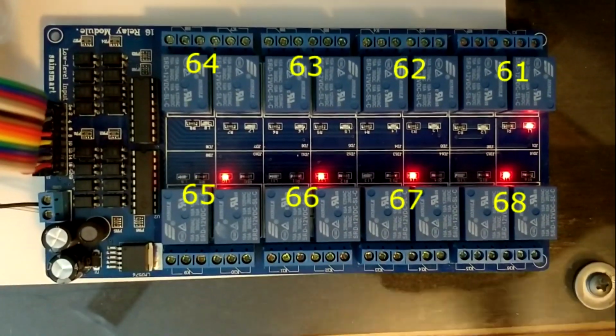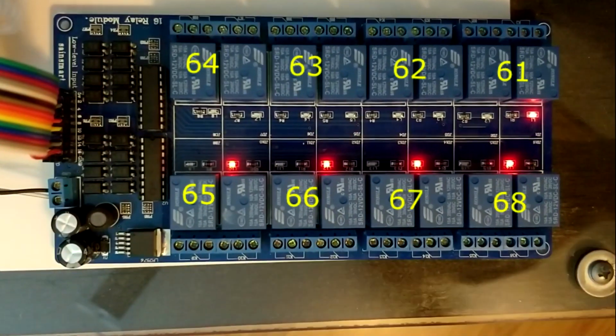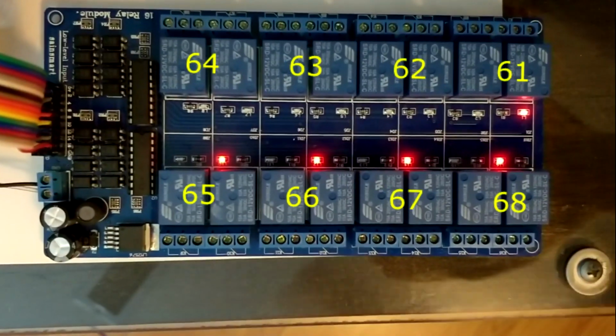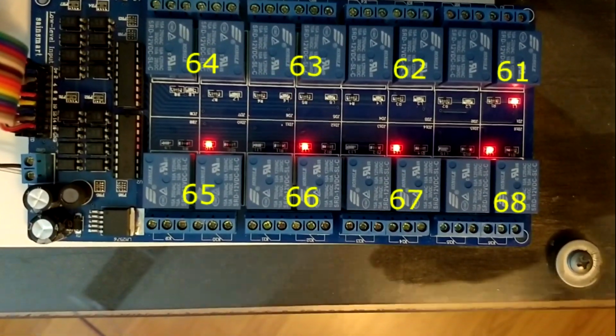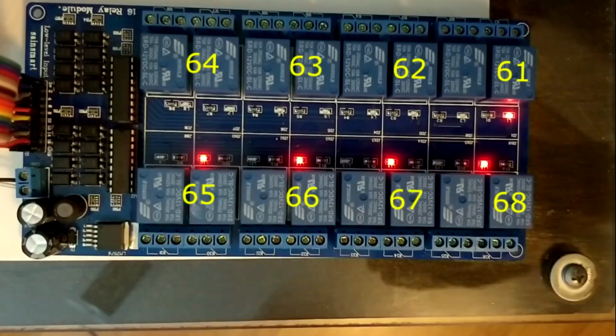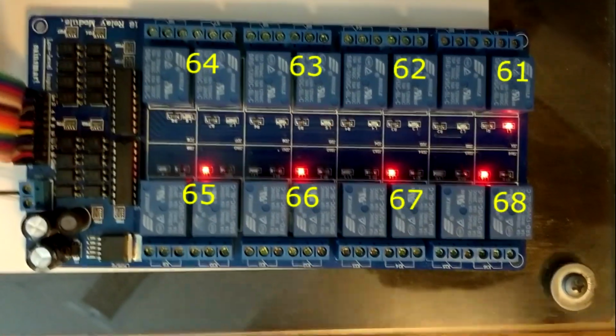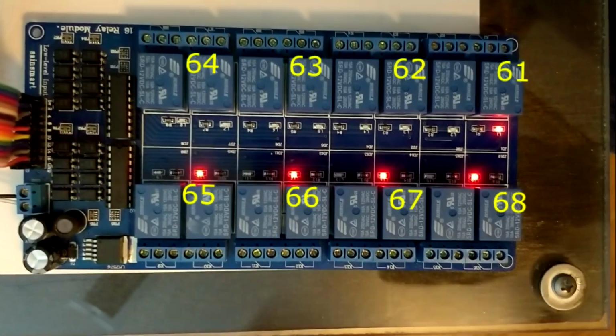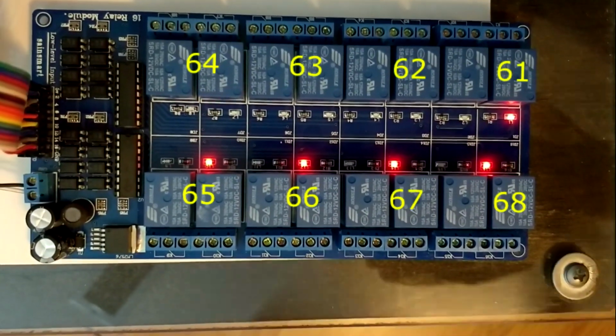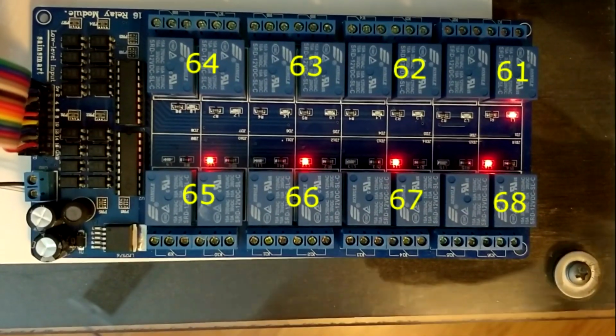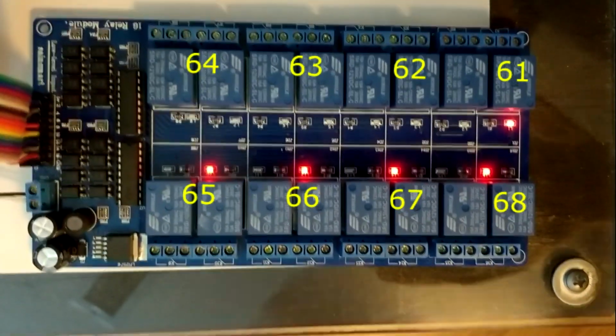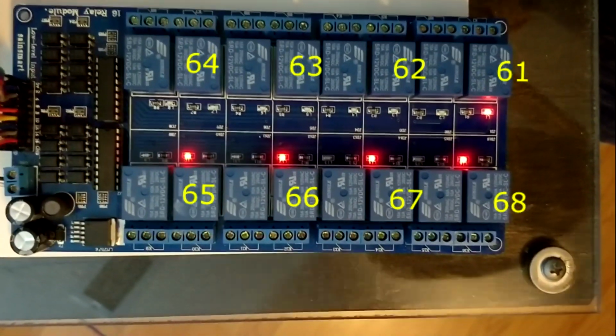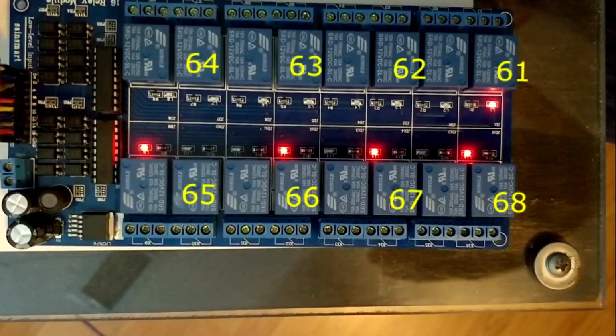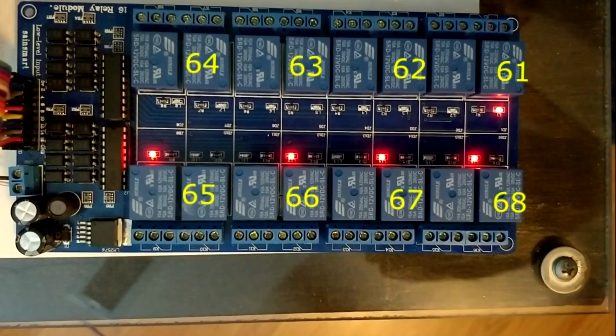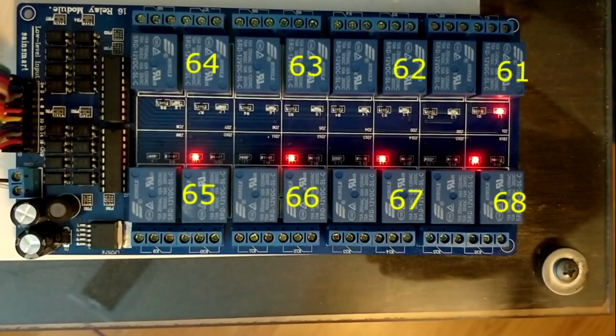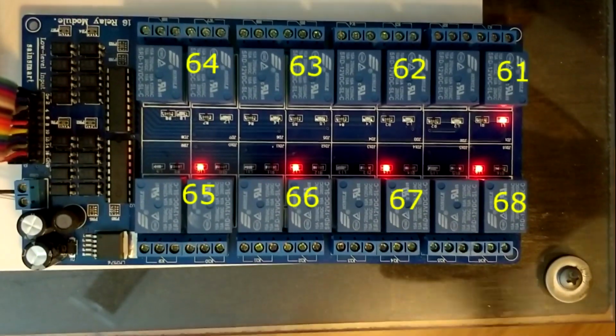That's good. The next one, 63, would be the 400 millisecond activation. So that's 400 milliseconds here. And 64 would be the 200 milliseconds. And that's 200 milliseconds. 65, and the next ones should be permanently on, and they stay permanently on. So everything working as expected.